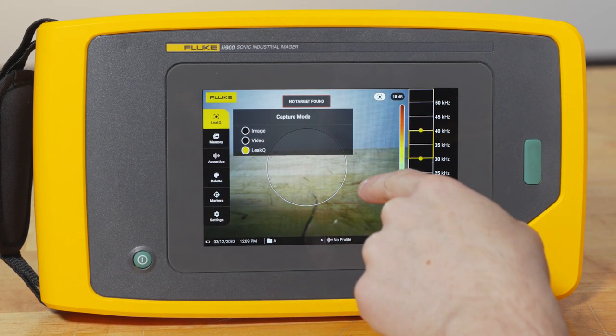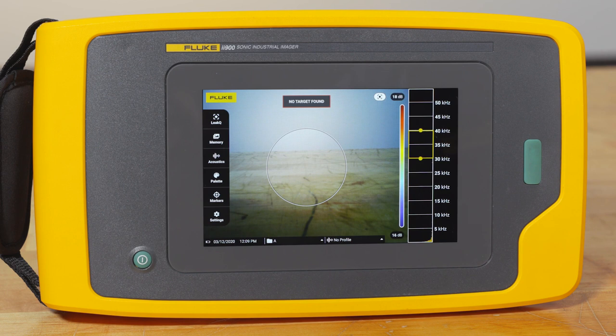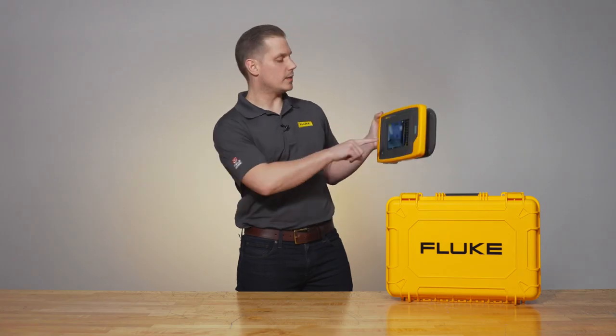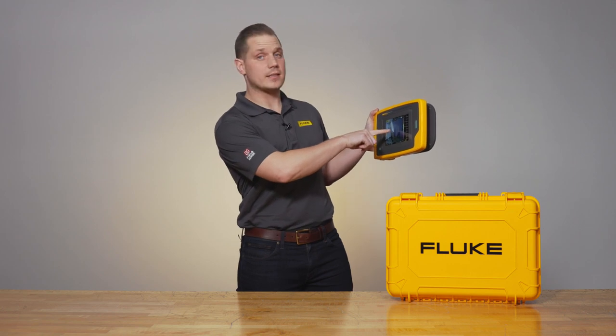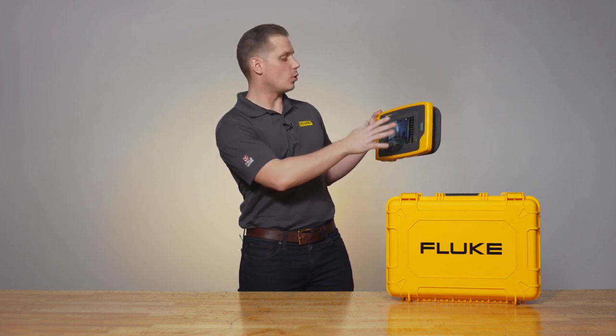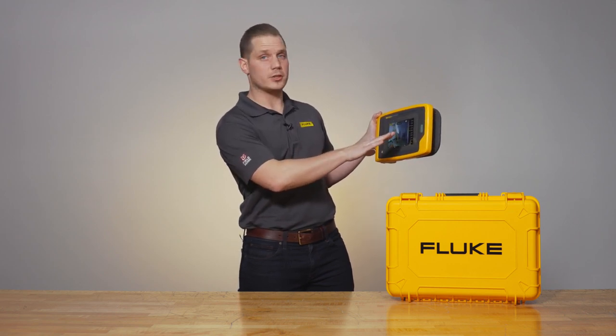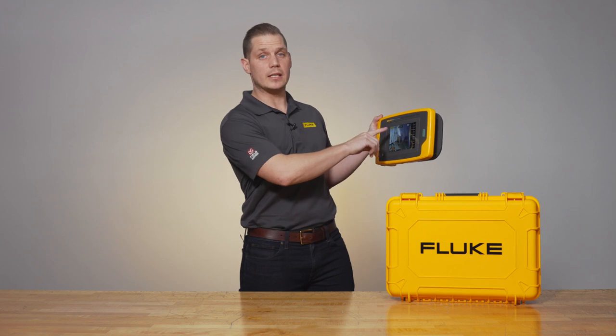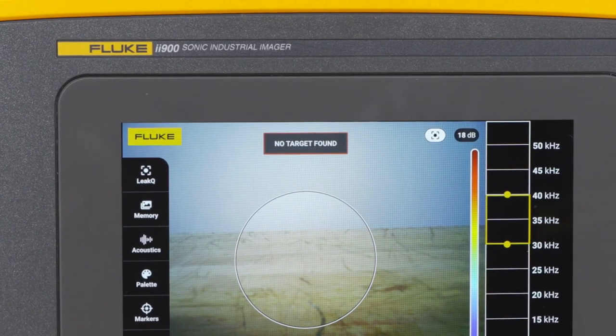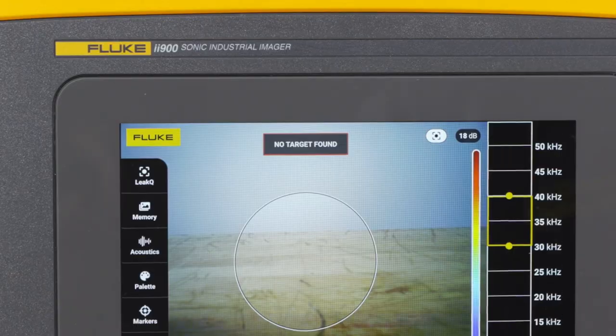Once you see that circle populate in the center of the screen, you'll know you're in LeakQ mode and you can go capture some images. Remember, the key is to get the leak inside the circle in the center of the screen. Even if you're seeing noise, reflections, or a leak outside of that circle, you're going to see this icon above that says no target found.